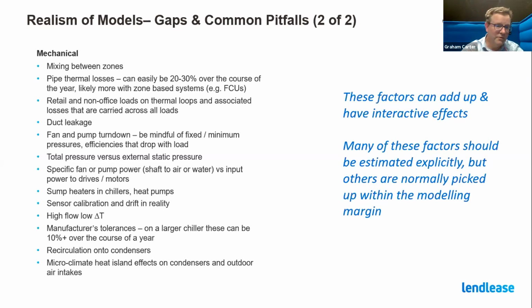With heat pumps and air-cooled chillers, you will get recirculation onto those, and that will bias the temperature onto them, which affects the efficiency. And then you look at where that equipment's placed on the roof. It may be biased by warming from the roof itself, warming from the microclimate or the urban heat island effects around the building. And this is particularly, we've seen it on shopping centers where you've got quite large roofs and you can get a 3, 4, 5 degree bias on your condensers relative to a weather file. So it becomes pretty substantial.